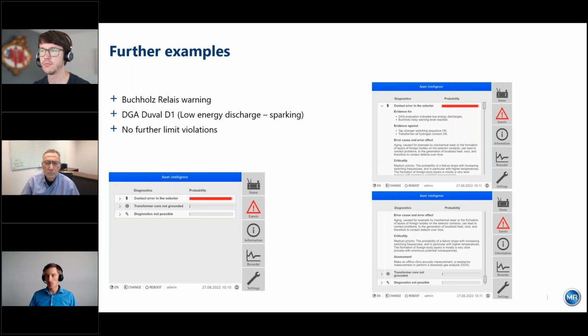In the first example we had a very probable shorted winding. In this second example, let's assume we also have a Buchholz relay warning, but this time instead of H2 we have a Duval D1 area, which means a low energy discharge, i.e. sparking. Here you can see it has nothing to do with the winding, but is due to a contact error in the selector — a problem with the OLTC. Again, you can see it's very probable, the bar is almost completely full, and we always explain why we come to this conclusion.